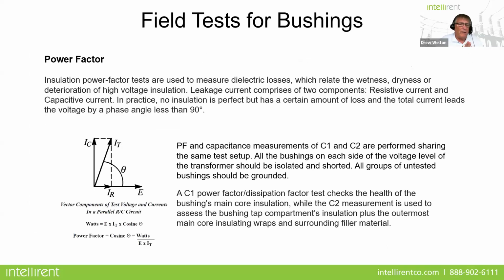Okay, so how do we test for moisture? Well, how do we test for the general health of bushings as well? The first thing that we all know, one of the tests that we do, is of course power factor testing. Insulation power factor tests are used to measure dielectric loss, and that can relate to wetness, dryness, deterioration of high voltage insulation, and leakage current.